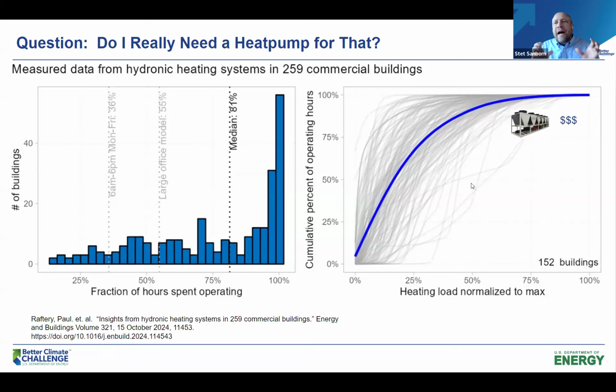There are very few hours in our commercial buildings where the heating system actually needs to be running at its peak load. And this goes back to Nora's question or point earlier, where what if your system was oversized? Almost every building that I go into to do an audit, the heating system has been oversized. It's never operating at full capacity. So when we're thinking about cost, one of the other really important questions to ask ourselves is, do I really want to install a heat pump for that last 25% or 10% of hours, covering this huge cost, but running maybe 50 hours a year? That's a huge investment for very marginal, minimal savings on GHG impact.